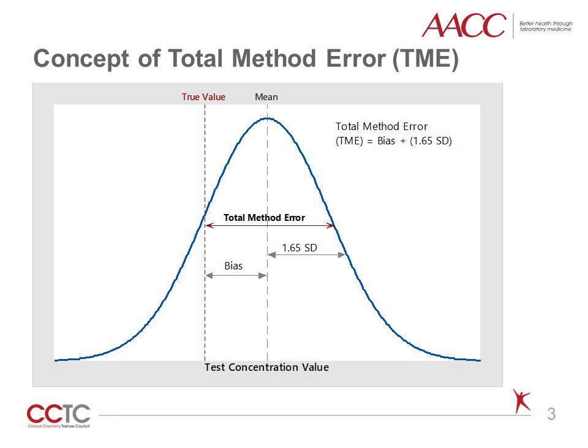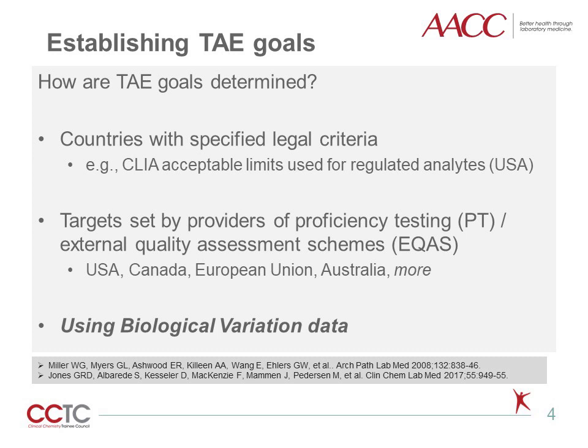Published biological variation estimates for a test analyte allow us to apply specific cutoff values to evaluate these components of method error, as illustrated in the figure. Establishing analytical quality goals for TAE has a rich history. These may be based on legal requirements such as CLIA laws in the United States, or set by providers of proficiency testing and external quality assessment scheme programs. As biological variation ranges differ across test analytes and improved estimates are readily accessible, there is renewed attention on establishing TAE goals using biological variation data. This is the focus of this pearl.